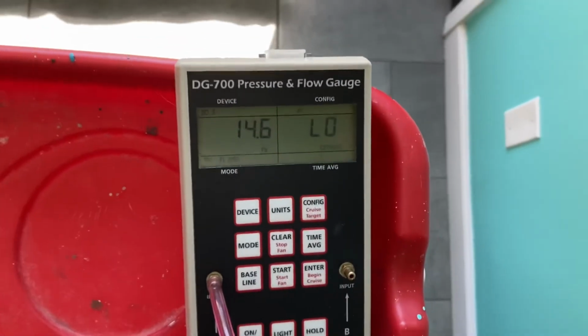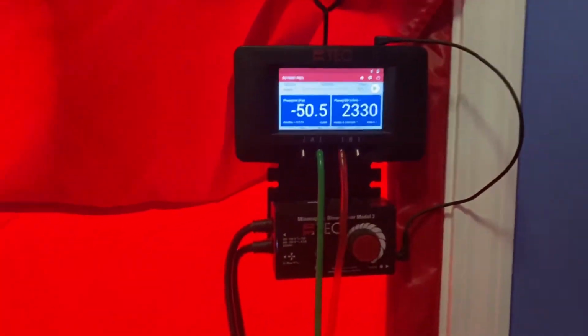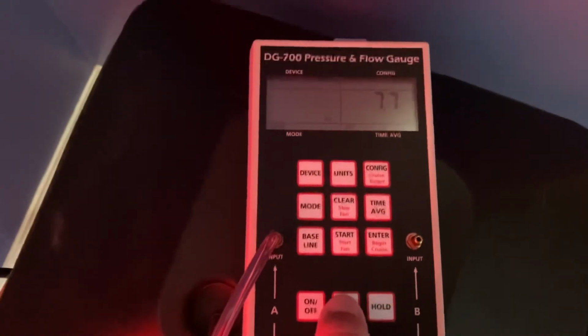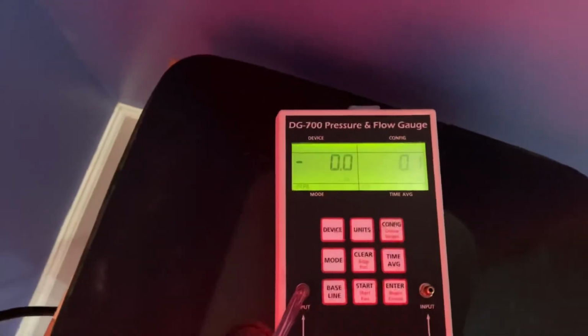You can also do this if you've got an old 700 lying around or any extra manometer. Just leave your blower door going and turn your manometer on inside the space with the fan running. It'll turn on already calibrated, ready to go, and you can run around and do your pressure pan readings. This is a lot nicer than tearing the 1000 off of your blower door and carrying it around. It's just a pretty good use for the old 700s.